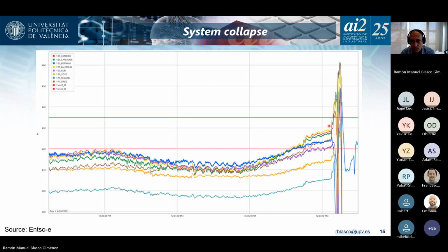Finally, before the voltage went above 435 kV, there were some disconnections at this point, and then a lot of generation was lost. There was no capability to control the voltage at that time, and then there was this massive overvoltage and disconnection of the whole system. Again, this bit here, we are talking about 5 seconds.